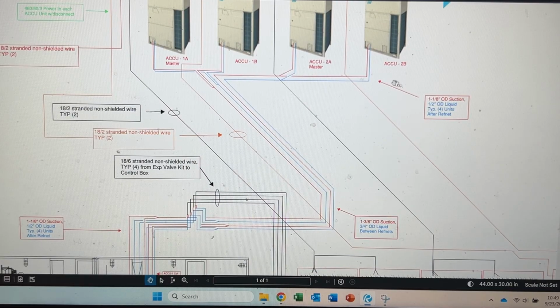So I size up the refrigerant as it's drawn here, based off the submittal. I got the sizing over here so the installers know what the size points will be for refrigeration. I put in where the ref nets are going and what that orientation will look like. This one was a little tricky with having 2 sets of ref nets, so definitely getting the orientation right is critical.